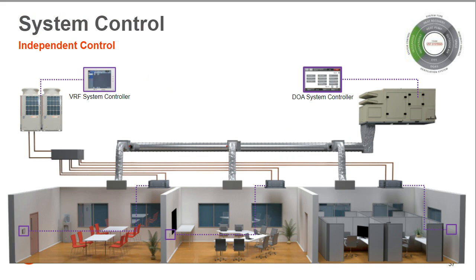VRF system designs have the capability to operate with a variety of control options. One of those control options is to independently control both the VRF and DOAS equipment separately. An independent control system will often be simple to design and install. It should also result in the lowest cost approach to control a VRF building solution. But that simplicity will come with some disadvantages.